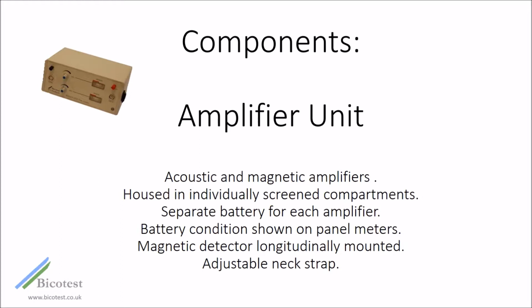The amplifier unit consists of a plastic housing which contains both the acoustic and magnetic amplifiers, the magnetic detector and the battery supply. It is fitted with a metal top plate on which are mounted the controls, display meters and connecting sockets for the acoustic pickup and the headphones. The acoustic and magnetic amplifiers are contained within separate screened compartments to prevent cross-coupling, and a separate battery for each amplifier further reduces the possibility of the signal from one channel affecting the other.